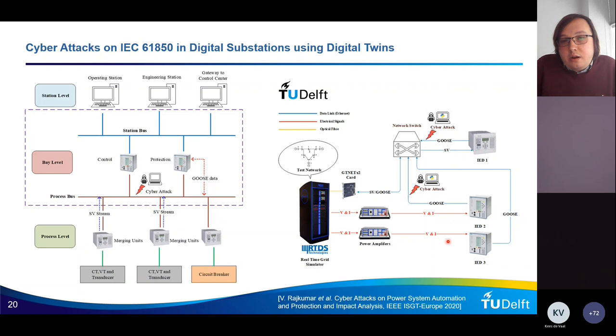Now, with this infrastructure, we can do various types of cyber attacks. And one simple cyber attack would be to monitor the communication traffic through this network switch, just like it would happen in the substation, capture GOOSE packets and sample values, and try to manipulate them to make the intelligent electronic devices think that there is a short circuit, or a problem with the power system operation, so they would trip a circuit breaker, or we just make the actuators think that the intelligent electronic devices are instructing them to open. So with this real-time digital simulator, with this digital twin, we could assess what would be the impact on power system stability, power system operation, and how this can cause cascading failures and a blackout.